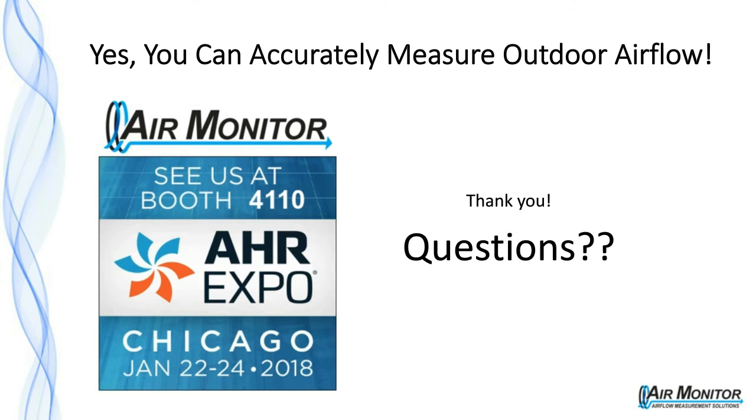The next question is, do you foresee a problem with verifying airflow at another location, such as the cooling coil? This considers the units running on 100% outside air during the testing. I think that might be acceptable. It really depends on how you are trying to perform that measurement. Right downstream of the cooling coil, right upstream? What are the other conditions in that location?